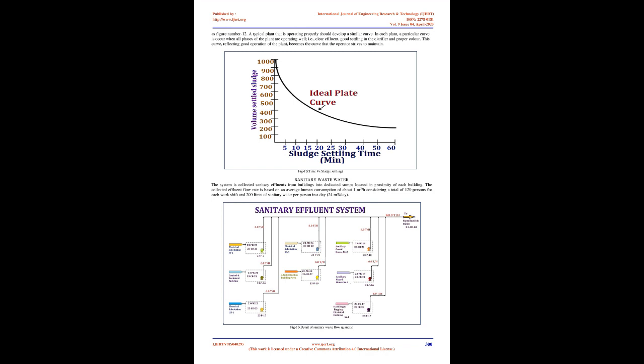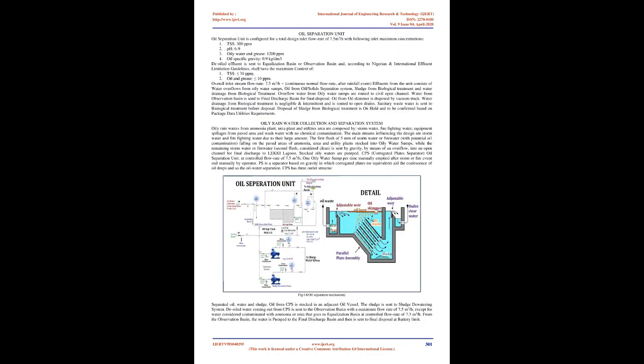Final discharge basin. Final discharge basin collects the blow-down water and treated water. Water is pumped out of the basin by 23P40A/B/C/D pumps to the BL raw water treatment plant. Urea wastewater treatments. Provision of separate high-pressure urea hydrolyzer section for treatment of 158 M3/HR process water generated during urea production process from both Train 1 and Train 2. Finally, treated water is of such a good quality that it is used as boiler feed water, as shown in the figure 15.